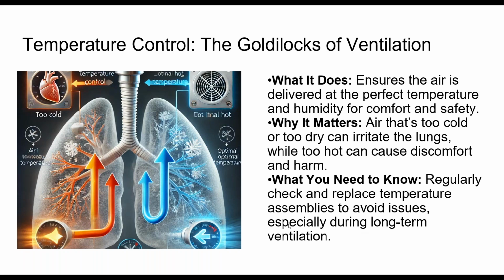But the reason why is because those sensors can fail, and they can fail either gradually or catastrophically. If they fail gradually, you're delivering the wrong temperature to the patient because that feedback loop from the sensor to the humidifier is potentially off just enough that you are delivering either too cold or too hot.